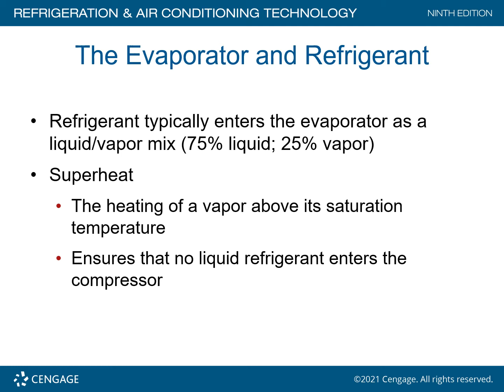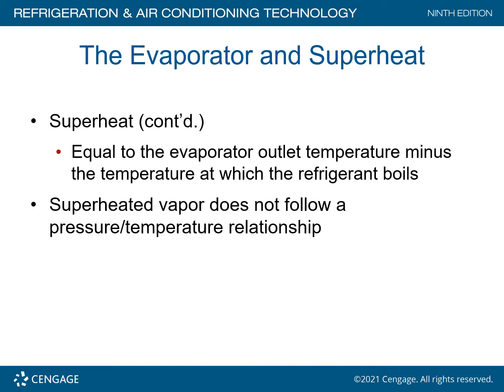Evaporator and superheat. Superheat is equal to the evaporator outlet temperature minus the temperature at which the refrigerant boils. So basically, you're going to have the saturation temperature, which is published for the refrigerant used, and the actual measured temperature. The difference between the two is going to indicate the superheat value that is applied at this particular instant. Superheated vapor does not follow a pressure-temperature relationship, so please don't look for a chart trying to figure out superheat. This is calculated based on the refrigerant, its corresponding saturation temperature versus the actual temperature. It is very important you have accurate thermometers in order to measure superheat.